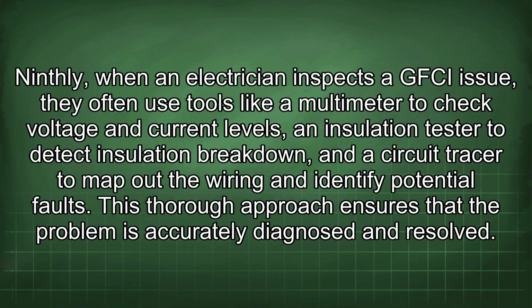9. When an electrician inspects a GFCI issue, they often use tools like a multimeter to check voltage and current levels, an insulation tester to detect insulation breakdown, and a circuit tracer to map out the wiring and identify potential faults. This thorough approach ensures that the problem is accurately diagnosed and resolved.